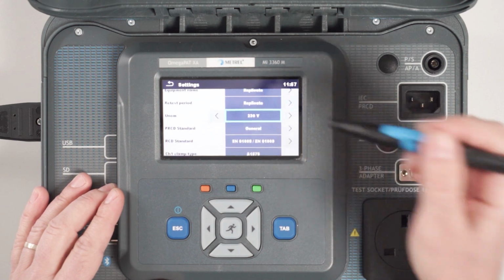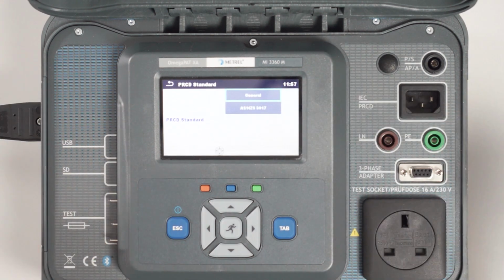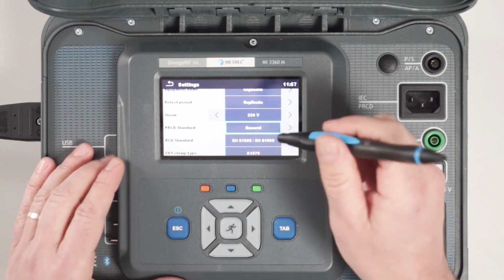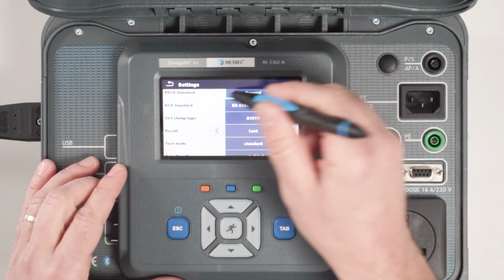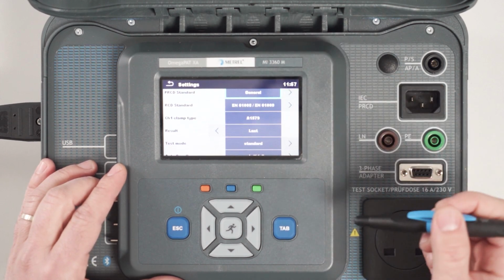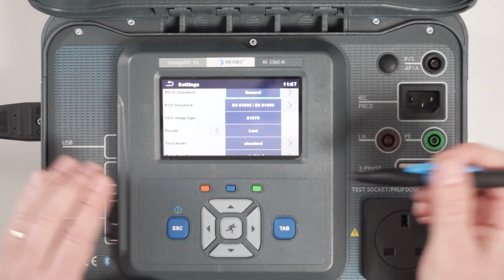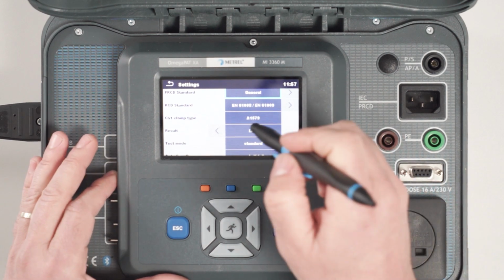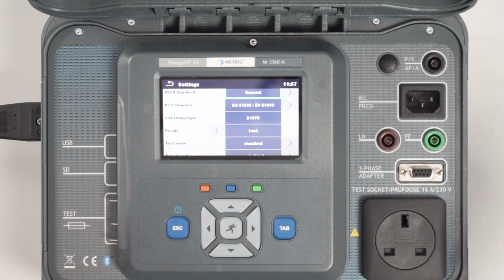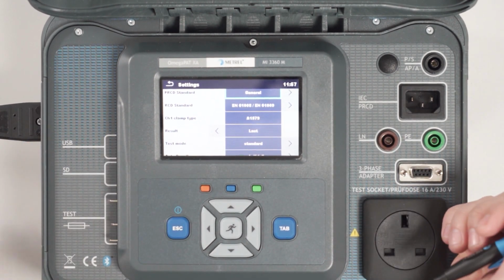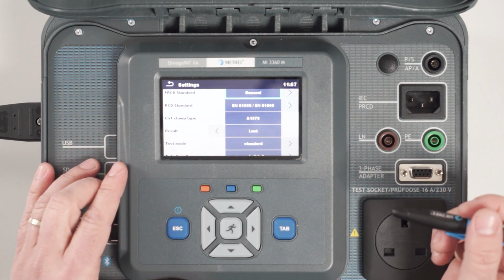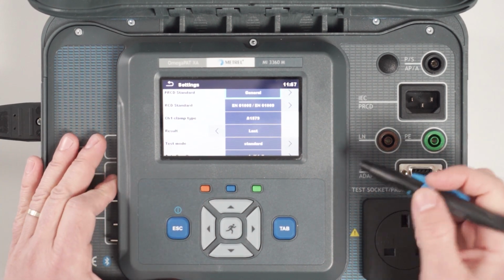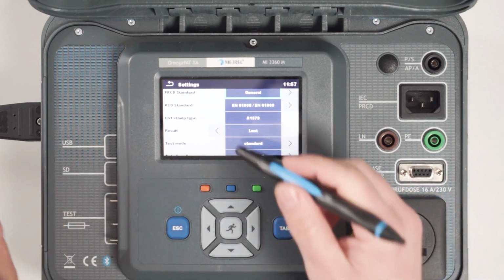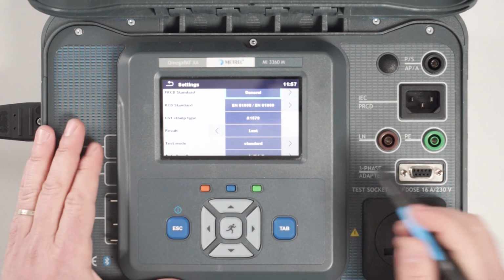Then we have here the possibility to choose different nominal voltage. Also we can choose between different standards, general or this Australian standard. This is for portable RCD and also for RCD. We can, as I mentioned before, also connect very precise external current clamps from the side of the instrument for measuring leakage currents. And here it's also one tricky feature.